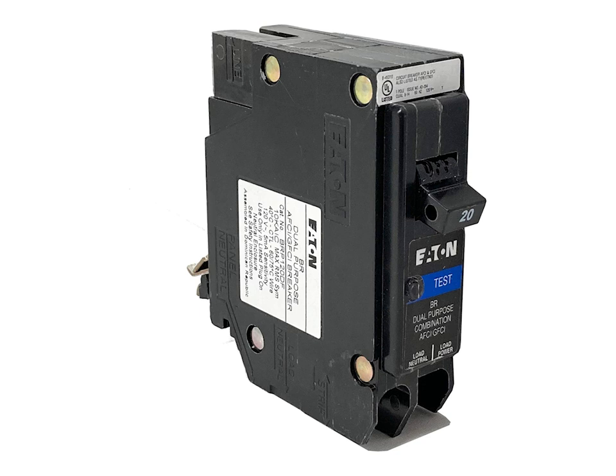Also, GFCI protected receptacles are required in bathrooms, garages, crawl spaces, basements, laundry rooms, and areas where a water source is present. The only circuits that don't need AFCI or GFCI protection are dedicated light or smoke alarm circuits. In my build, the only circuit we have like this is the smoke alarm circuit. Smoke alarms are not permitted to be supplied by a branch circuit protected by a combo, ground, or arc fault circuit interrupter, GFCI, AFCI, because during a fire situation, the interrupter may trip and potentially disable the smoke alarm. The GFCI, AFCI breakers help in preventing electrocution and your house burning down.